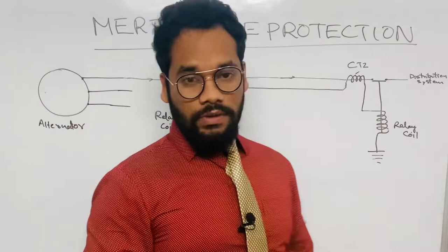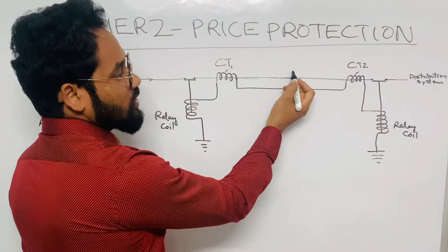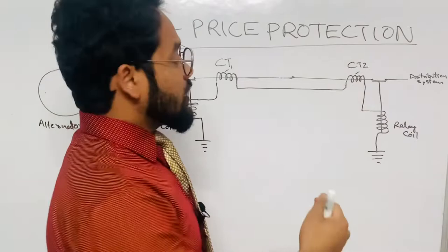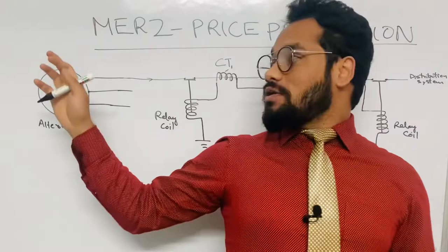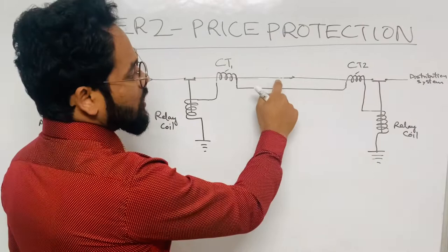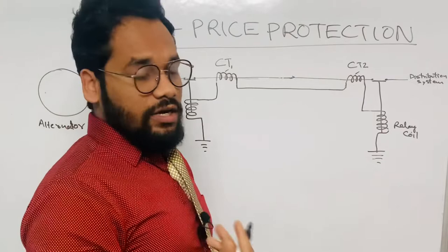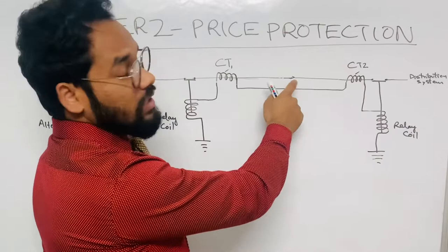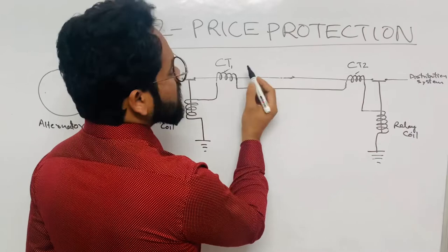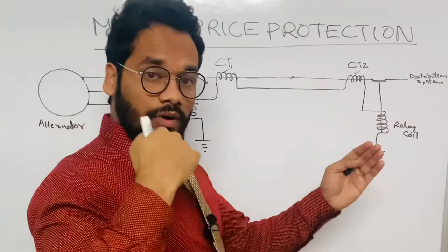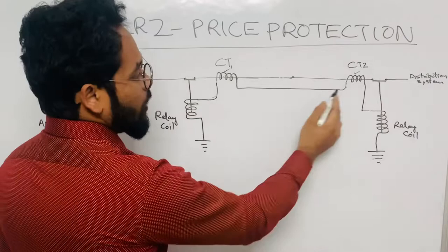Now suppose the feeder line has a fault — for example, it has short-circuited with the aircraft structure because the insulation was broken. More current will then be drawn from the alternator, which can even lead to burning of the alternator. In this fault scenario, the EMF induced in CT1 and CT2 will be different. Since the induced EMFs are different, current will start flowing in the relay circuit loop.